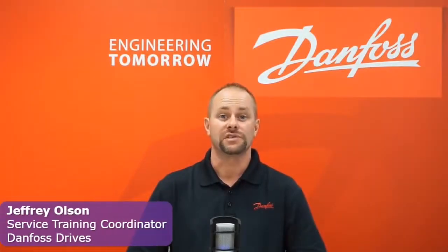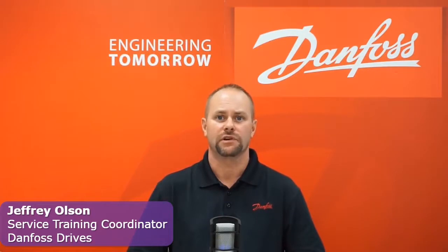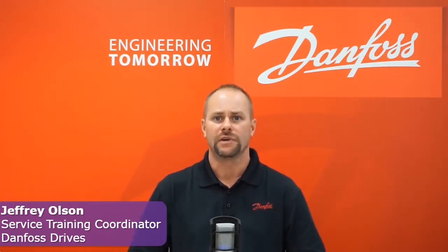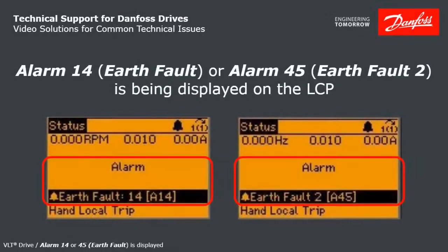Hello, my name is Jeff Olson, and I'm part of the training team here at Danfoss Drives North America. Today, I'm here to talk to you about two different alarms, both of which are caused by the exact same condition. The drive is tripped, and alarm 14 earth fault or alarm 45 earth fault 2 appears in the display.